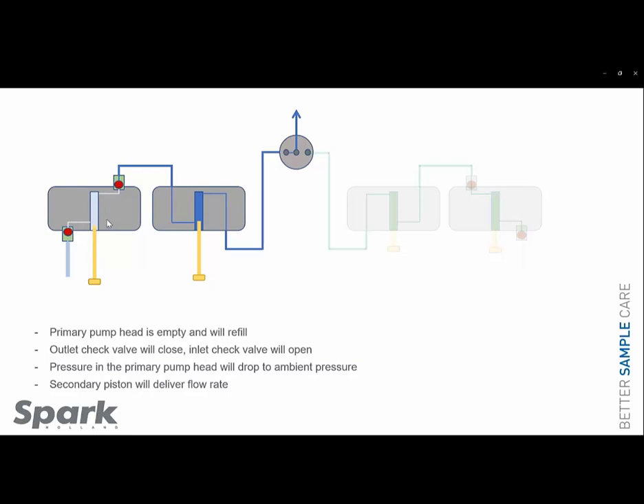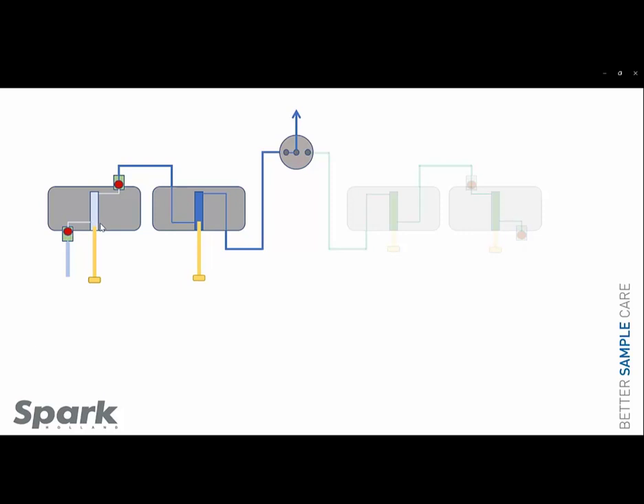The pressure inside the primary pump head is now ambient pressure. Therefore, the color in this pump head is lighter blue. Now the primary pump head is filled with mobile phase. The piston will move forward. The pressure inside the primary pump head will increase up to 6 bar below the system pressure.